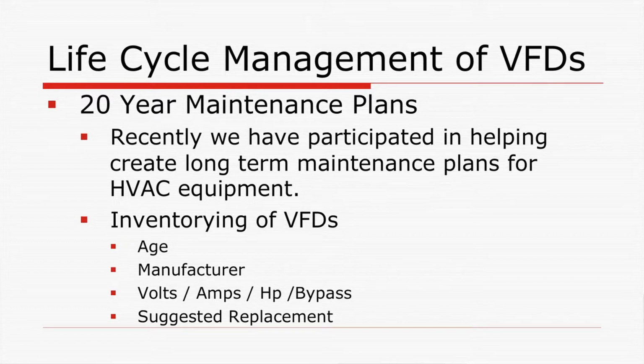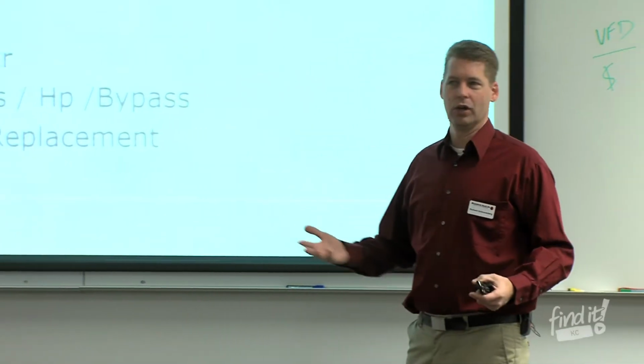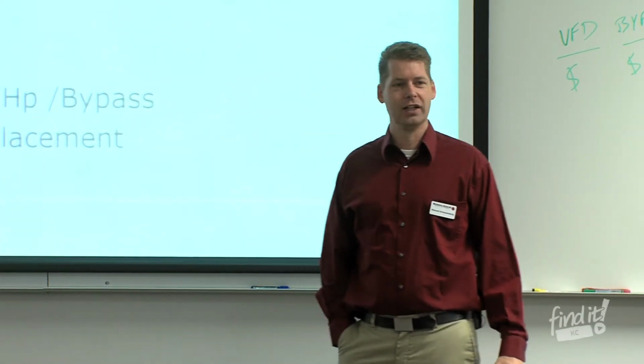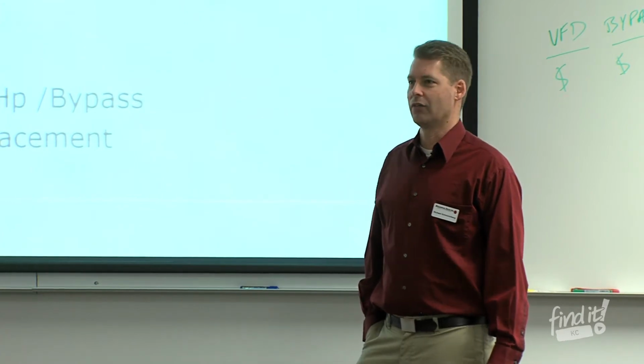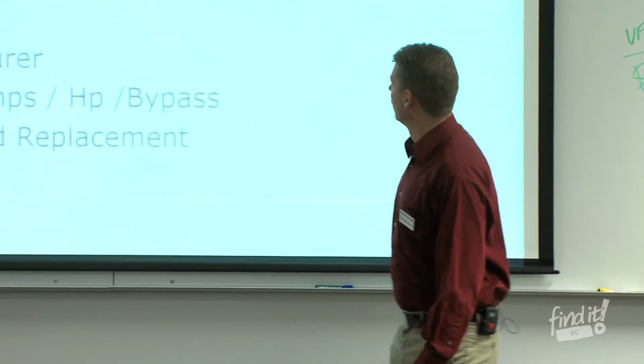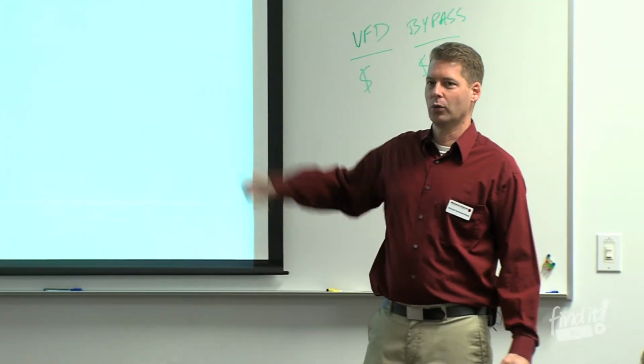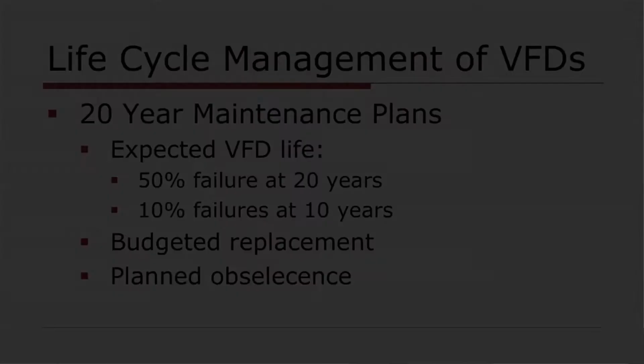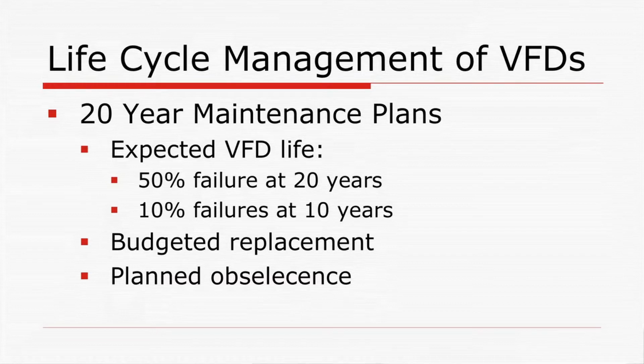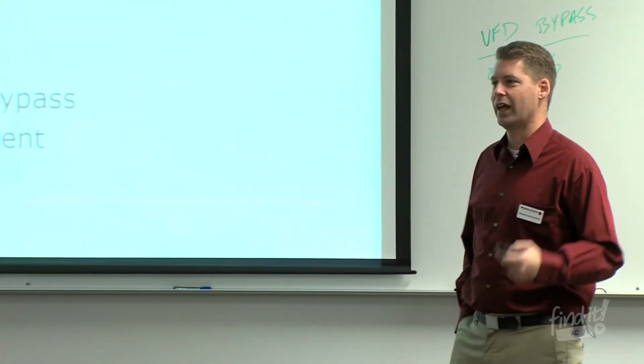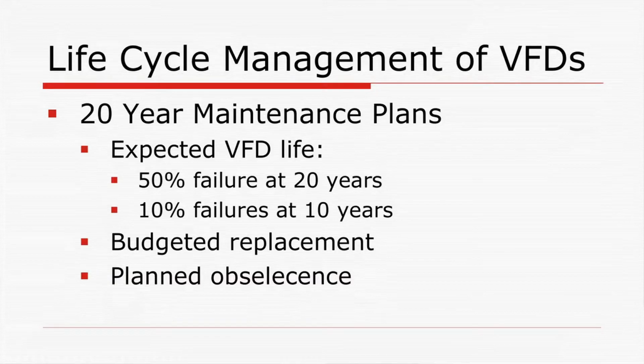Let's figure out what we're going to be needing so we can proactively predict what we're going to have to replace at certain times. You ask any manufacturer of any piece of equipment, they'll have an idea how long that piece of equipment is going to last. Everything wears out, right? So I went and inventoried the VFDs. I wrote down the age, the manufacturer, their volts, amps, hertz, whether it had a bypass or not, and gave them a suggested replacement for each of the VFDs on campus. Created a nice pretty report with lots of spreadsheets so they'd have some way of tracking their equipment by the mechanical room in this building, in this mechanical room, running this piece of equipment. They'd know what they'd have and be able to use it from that point forward.